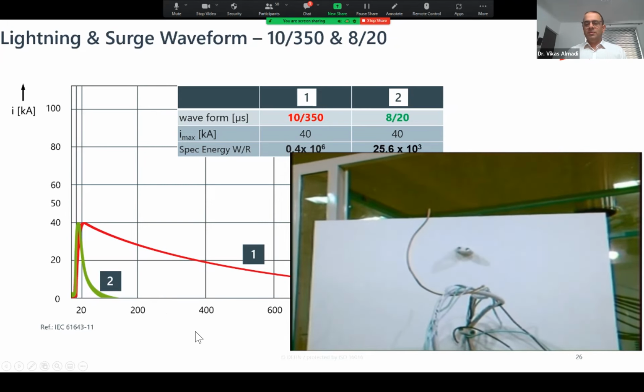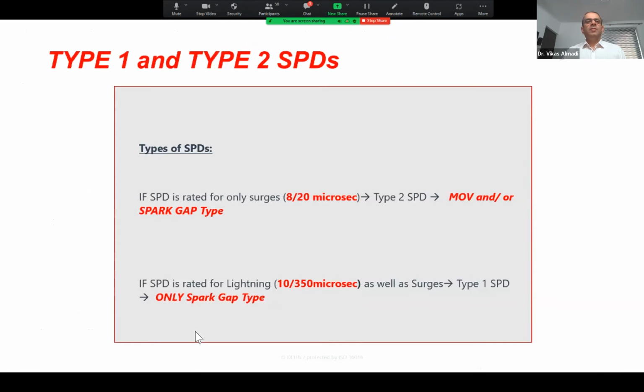Okay, so that is the reason there are two types of SPDs now. One type is type 1 SPD, which is rated for 10 by 350 microsecond, and the other SPD is rated for 8 by 20 microsecond. When we talk about 10 by 350 microsecond SPDs, they are known as type 1 SPDs. Normally, people use spark gaps here because spark gaps are more rugged than dissipating devices like MOVs. Some people are using MOVs, but at the same time, more data has to be asked.